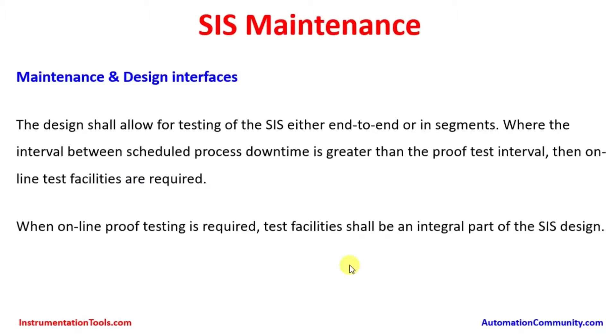Maintenance and design interfaces. Whenever plants are going into operation, there could be many kinds of interfaces between different groups for the safe operation of the plant. The design shall allow for testing of the SIS either end to end or in segments. Where the interval between scheduled process downtime is greater than the proof test interval, then online test facilities are required.